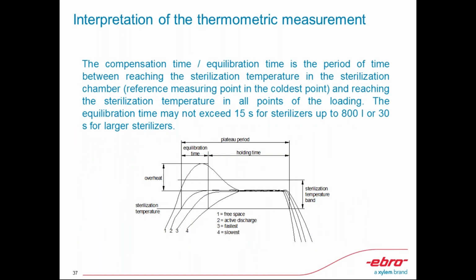When we are doing all these thermometric measurements, the only things that matter are temperature and pressure. With ETO, it's relative humidity and time, but these are all data points and will not mean anything until they are evaluated properly. We have the software, and I recommend the WinLog validation for a thorough and more accurate evaluation of your sterilization processes. So it's very important that we know that all those stages in the sterilization processes and cycles are met and their objectives are achieved.